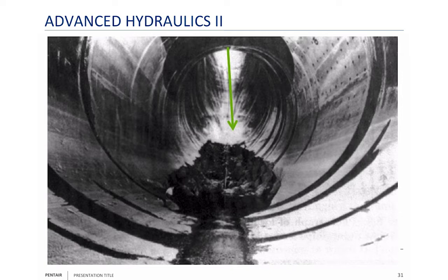And so when you look here, there's your sweeping elbow, all right? And if you look really carefully, that white dot right there in the pipe on this end of the cavitation damage, that's a man in a white shirt. The cavitation pipe here is 50 feet in diameter. The area that it affected is 115 feet long, 30 feet wide, and 45 feet deep. That's what he's looking into, a pit that's 45 feet deep.